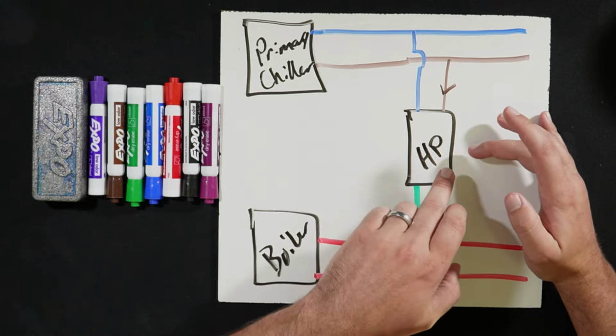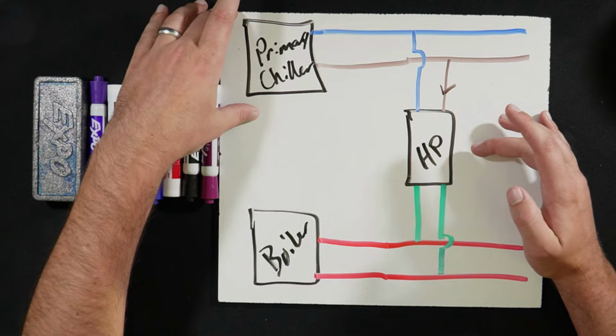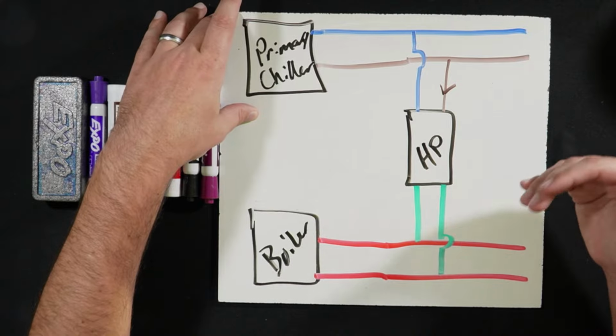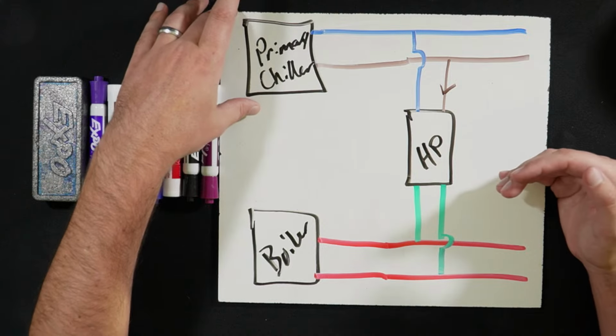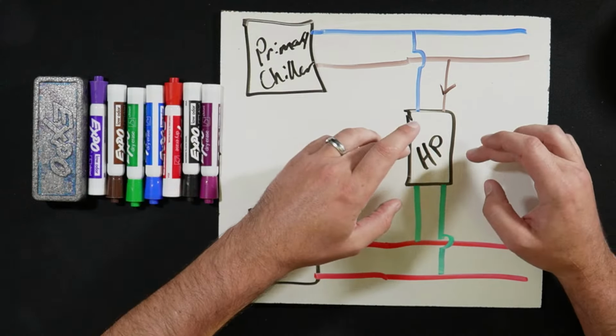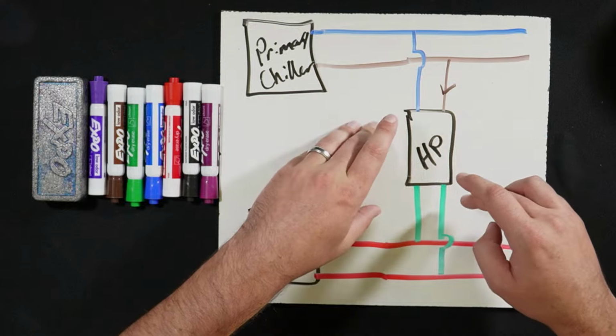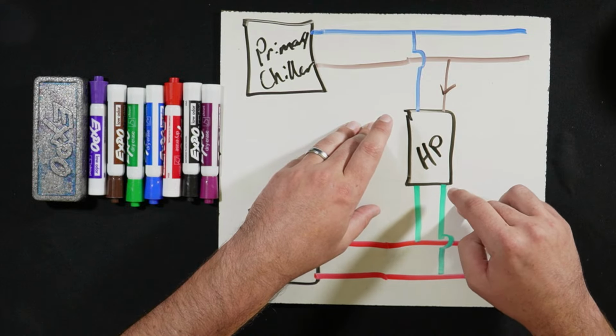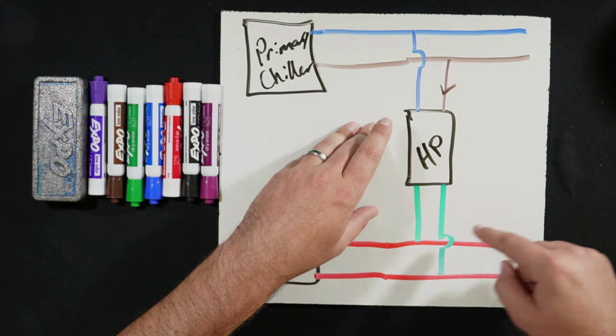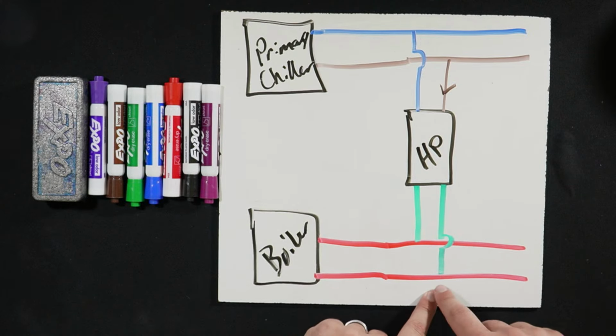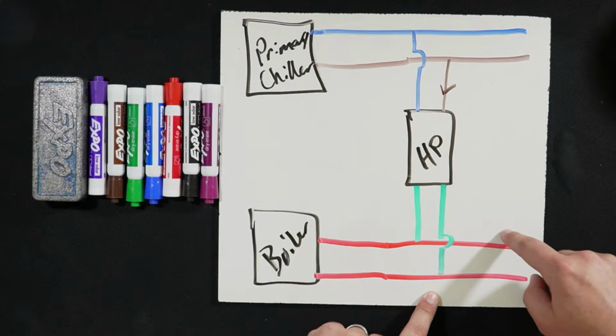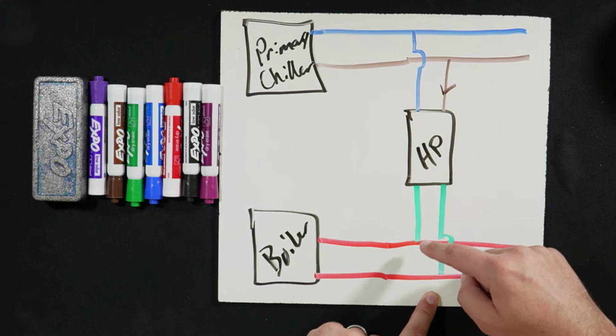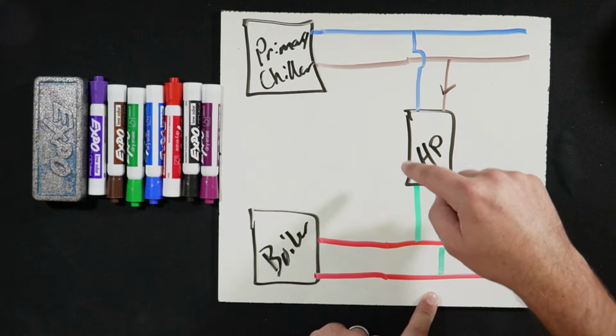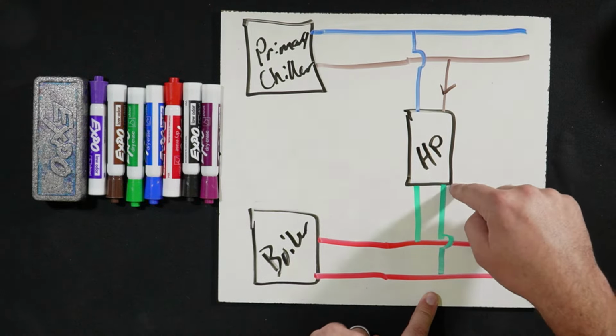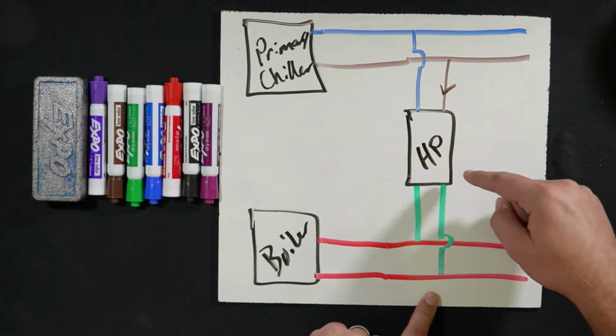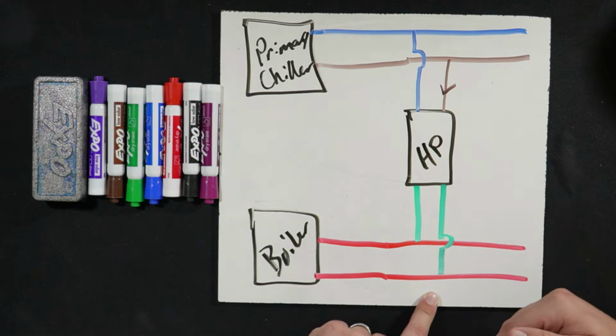So that's not where we want to operate our primary. That's very inefficient, and that's not necessary for our primary cooling system. But these heat pump chillers are designed to run at really high leaving water temperatures. And they're also designed to take in hot water temperatures, because you've got to think, if we've got, say, 140 going out, it may be 100 to 110 coming back in. So we're feeding 100-something degree water into the condenser of this heat pump and trying to produce back out that 120 to 140 degrees on the other side of it.